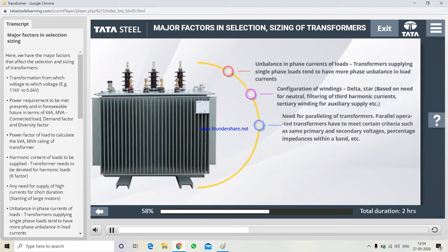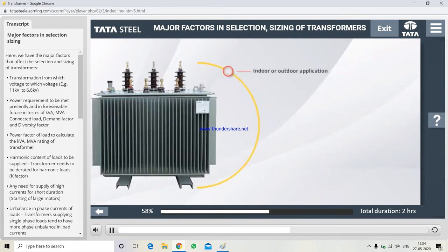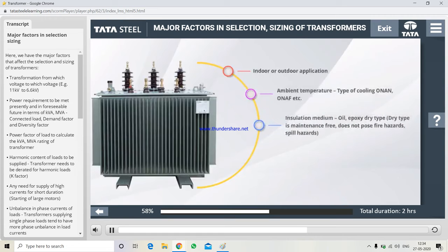Parallel operated transformers have to meet certain criteria such as same primary and secondary voltages, percentage impedances within a band, etc. Need for voltage adjustment. On-line or off-line tap changer. Voltage regulation and efficiency that is required. Indoor or outdoor application. Ambient temperature. Type of cooling. ONAN, ONAF, etc. Insulation medium. Oil, epoxy dry type.